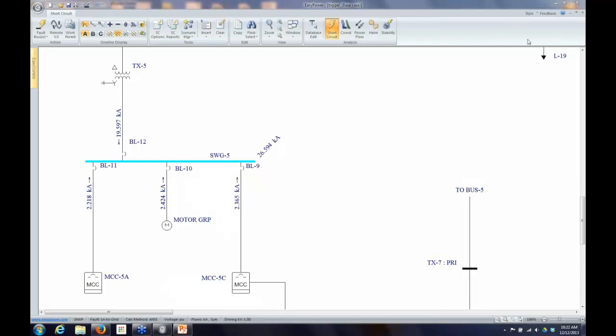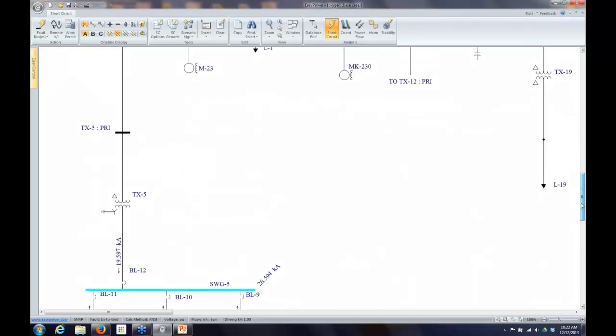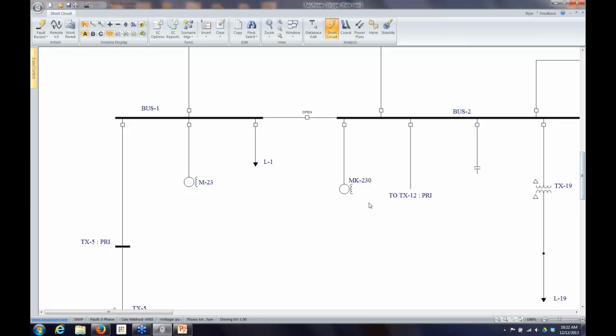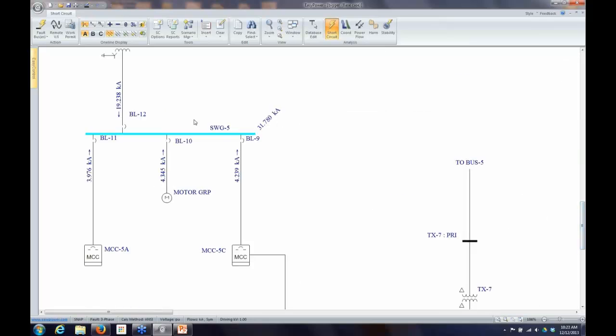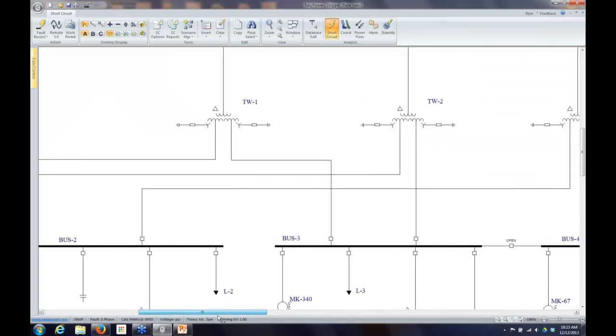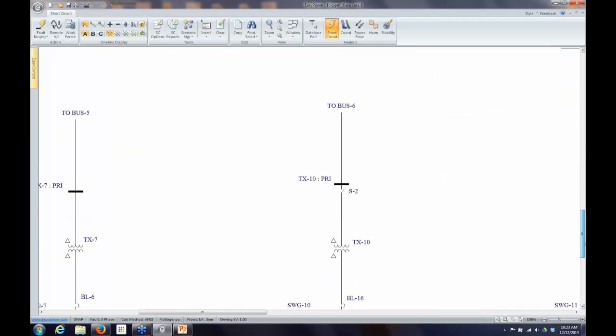Another really useful feature in EasyPower is what we call remote voltage and current. When I have a short circuit at a bus, the voltage collapses to zero there — we assume a bolted fault. The rest of the system is affected with a significant voltage sag depending on proximity to the fault. EasyPower gives us a way to display the voltage and current from any bus in the system for a fault at one particular bus.